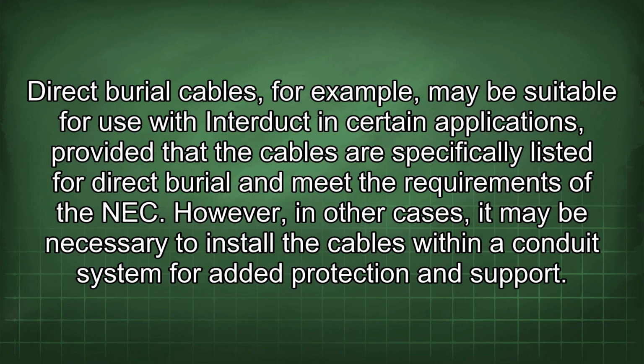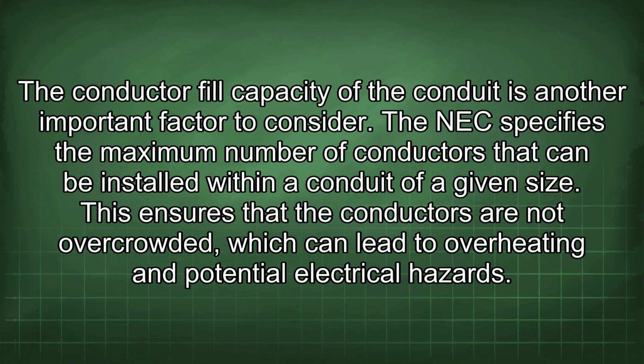Direct burial cables, for example, may be suitable for use with Interduct in certain applications, provided that the cables are specifically listed for direct burial and meet the requirements of the NEC. However, in other cases, it may be necessary to install the cables within a conduit system for added protection and support. The conductor fill capacity of the conduit is another important factor to consider.